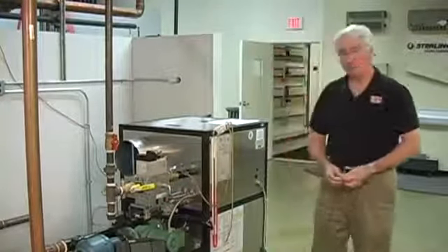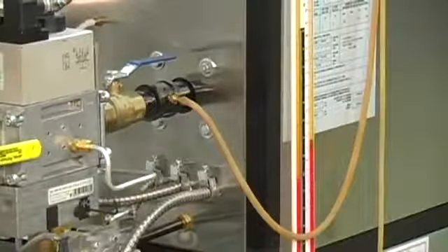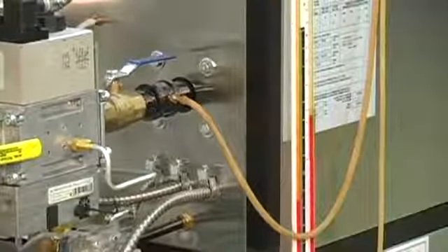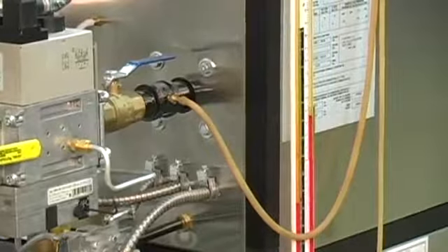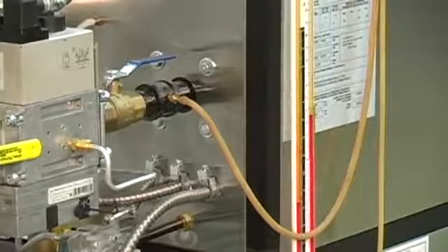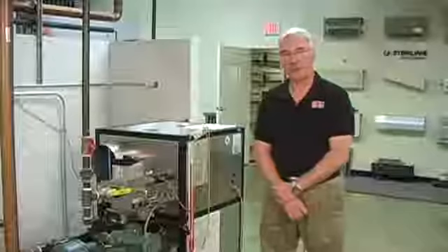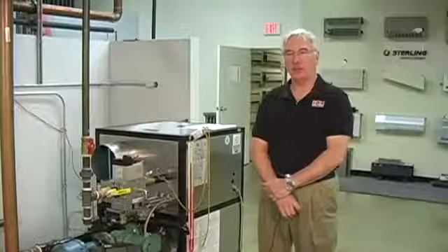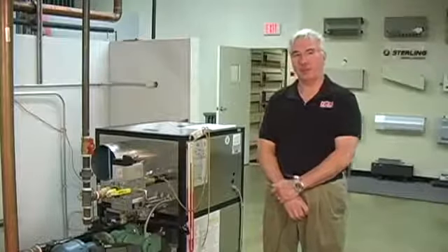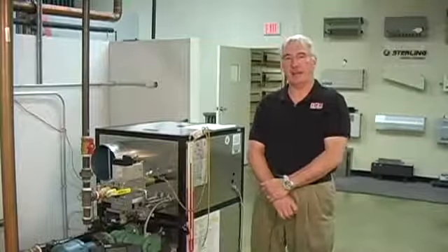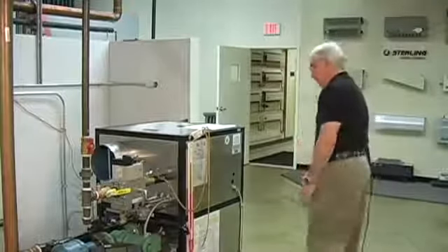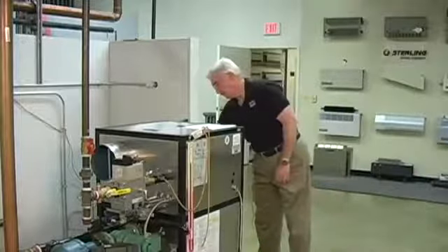At that time also you can check your gas pressure reading, which is on the last tapping before it enters the boiler. You can compare that with the values listed on the startup information on the control cabinet door. Once we're satisfied with our low fire combustion, we can then proceed to checking our high fire combustion. To accommodate that, we'll have to return back to the control cabinet and make a switch selection on our control panel to drive the unit to high fire.